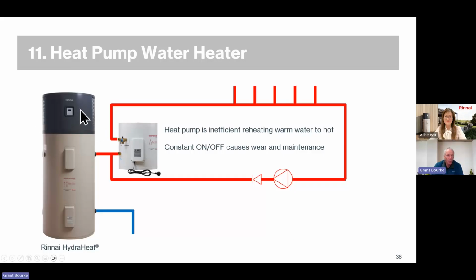It's coming out the top, but you still don't want these too close together because we've got a reasonable volume of air we want to get in that vent. There is a distance in the manual for the Hydra Heat that shows how far apart to put them to make sure you're not going to starve them of air.